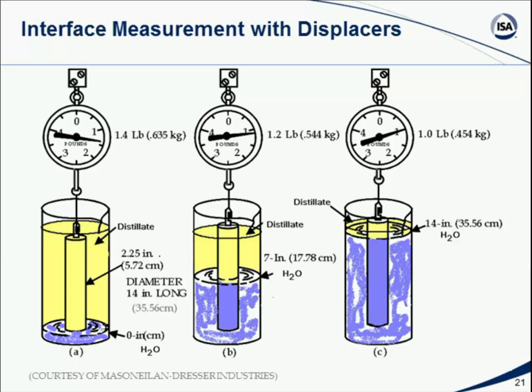Well, we'll go to the same concept here. In the first diagram on the left-hand side, we're showing the water level all the way down at the bottom, so we have no water in the tank. The tank, though, is fully filled with a distillate. So my displacer is hanging there, floating, shall we say, in the distillate. So it doesn't have the same weight. When it was hanging in midair, it weighed 15.8 pounds. Now it's hanging fully submerged in distillate, and it only weighs 1.4 pounds, because it's fully submerged.